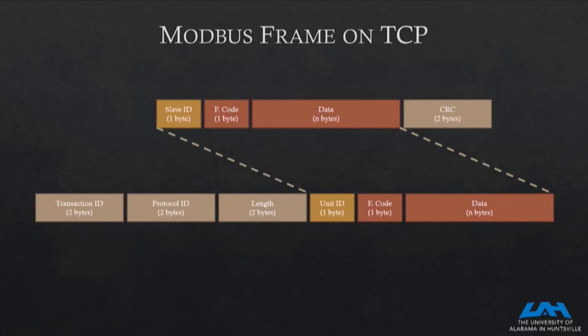They updated Modbus to make it compatible with TCP/IP networks. What it means is that they added a frame on top of the Modbus frame. So basically, it has a transaction ID to keep track of all the transactions you're making. If the host makes a transaction, it makes a random number on that transaction ID. So when it receives a response, it might receive a bunch of responses from the same slave device, and it will match the transaction ID to make sure that response is related to the query it was making.